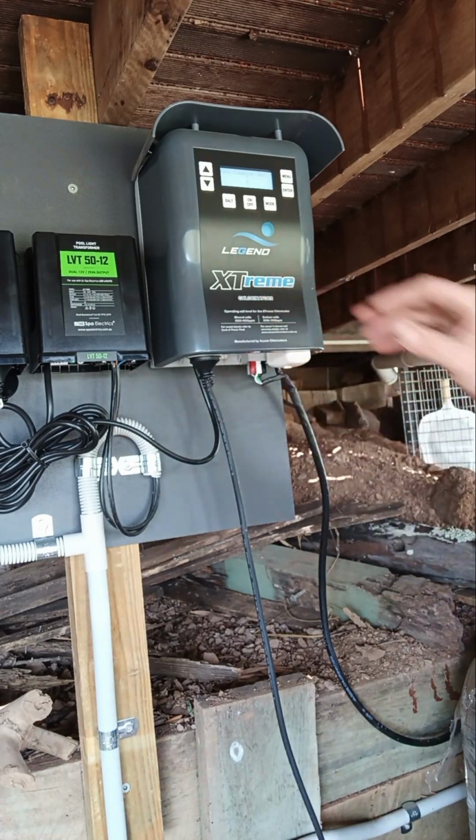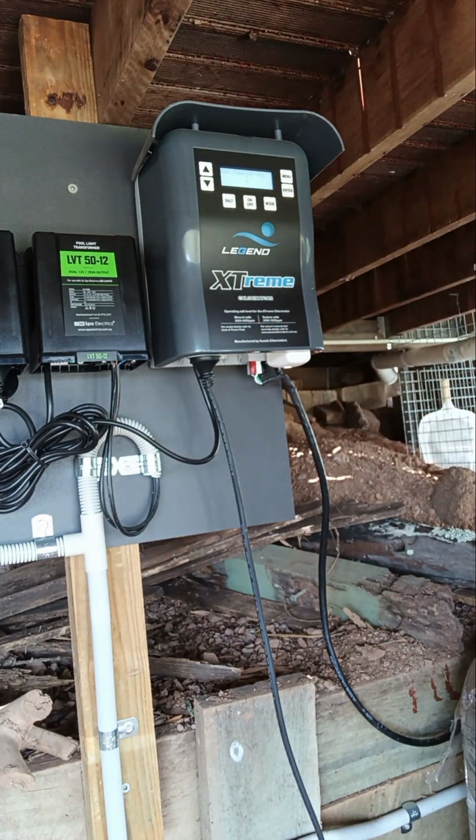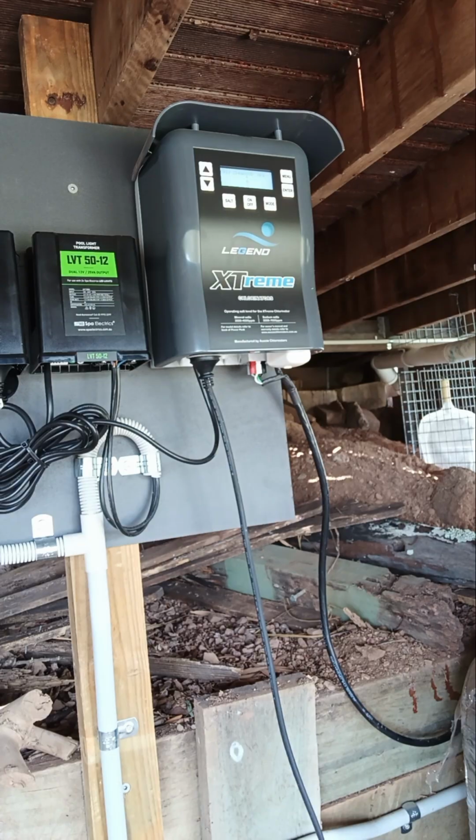What we'll notice is in the cell housing, if we see white calcification deposits building up, we can reduce the hours of the reverse polarity cycle. So if we're reversing every 8 hours and we need to shorten it to help break away the calcium, we can drop a few hours out of it and say every 6 hours. It helps clean off any calcium deposits building up inside the cell housing.